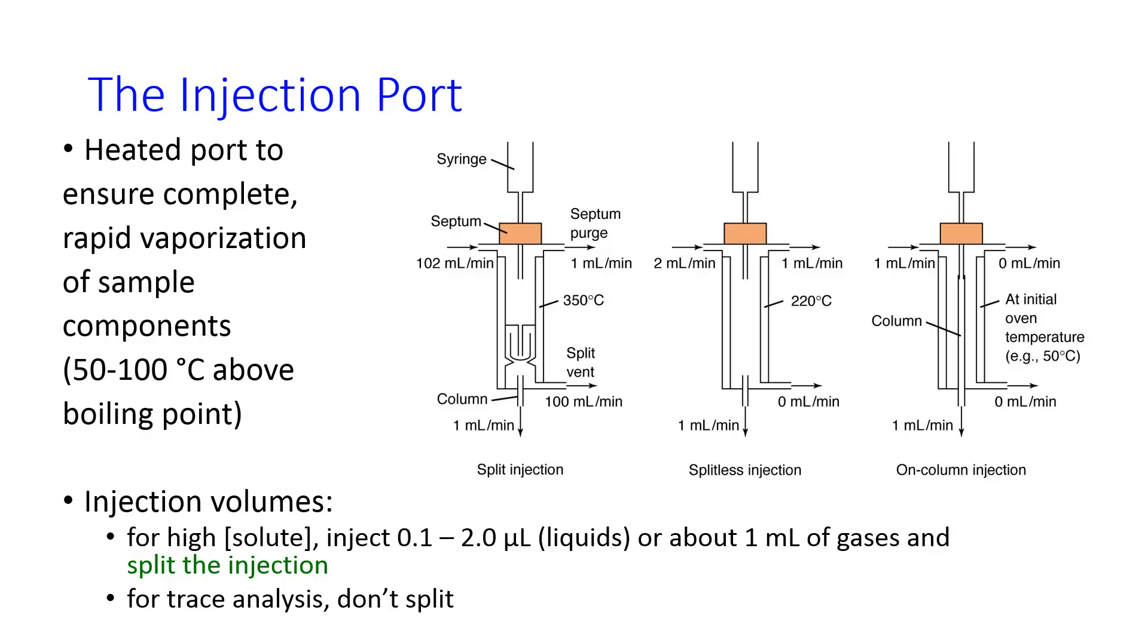When you have a high solute concentration, you can do what's called a split injection, where most of your injection goes to waste, and then a very small percentage goes onto the column. If you're doing a trace analysis where you have a very low solute concentration, you would not want to split, but you can inject directly onto the column.